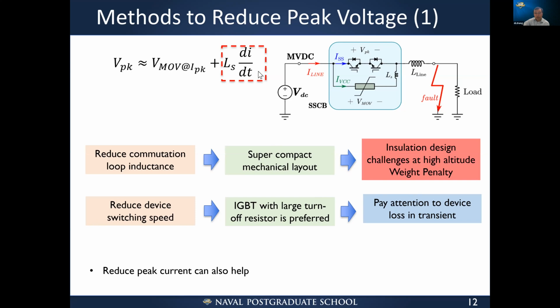Another way is to reduce the device switching speed. For example, we have used devices with large turn-off resistors. This is preferred because the penalty is high switching losses, but that is nothing for solid-state circuit breaker applications. We only care about conduction losses. So as long as the device can handle that, this is almost free for the design. And once you slow down the switching speed, it also brings a lot of design freedom for mechanical design, so I can play a lot of tricks in the mechanical design to optimize the volume and weight. And of course, if I can reduce the peak current, I can also reduce the di/dt indirectly.